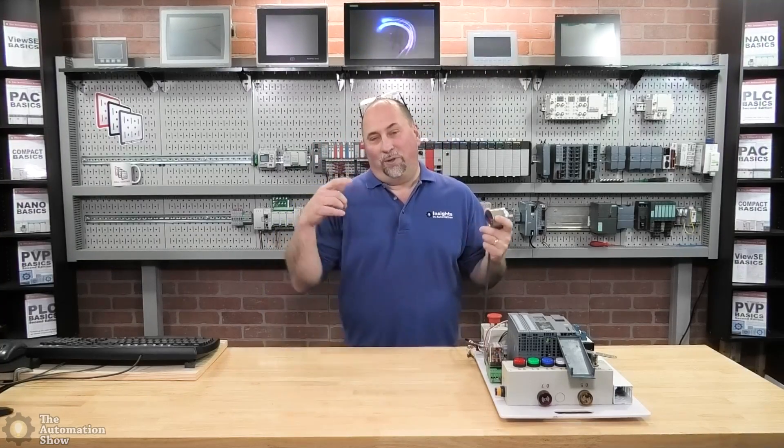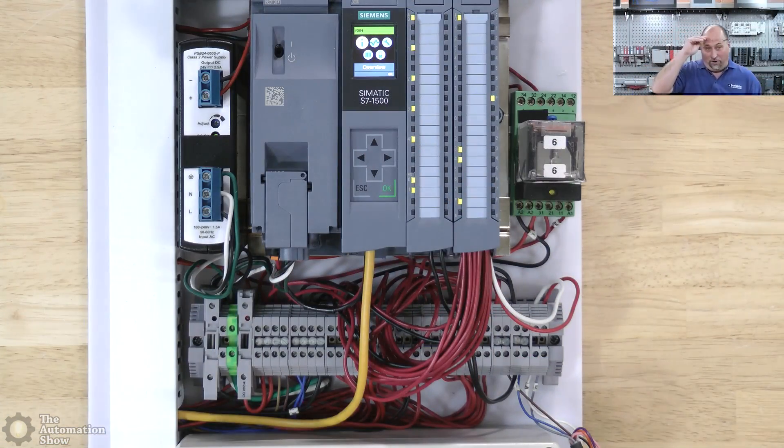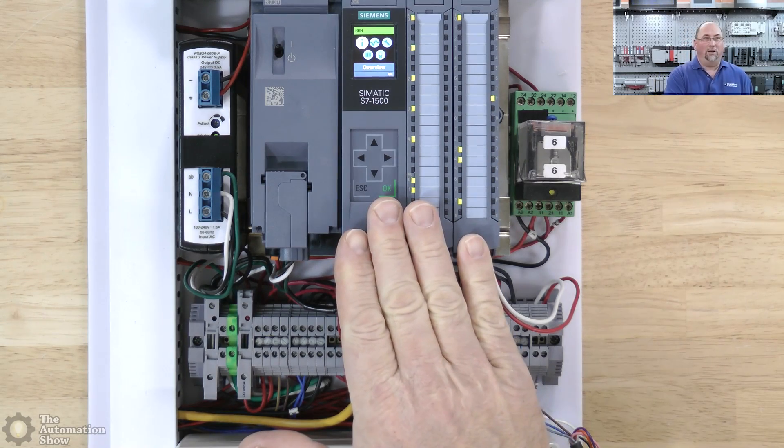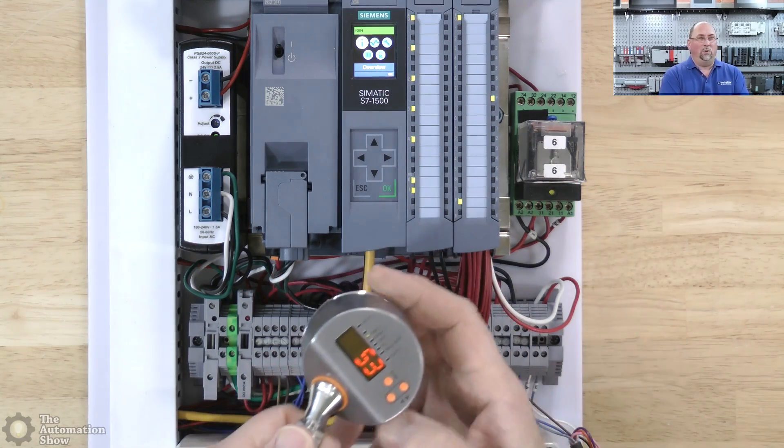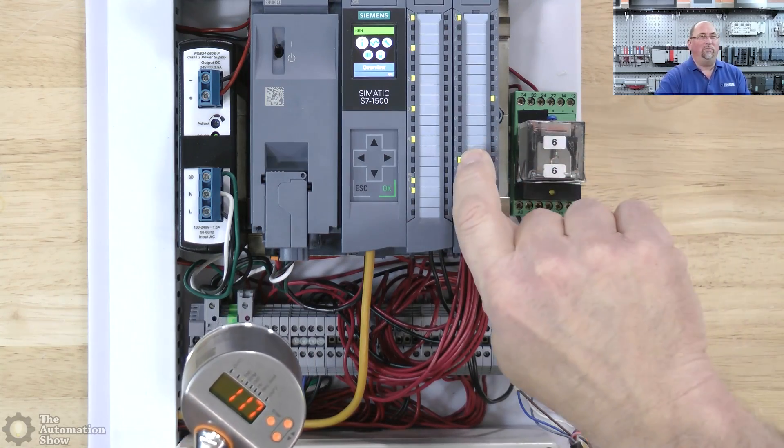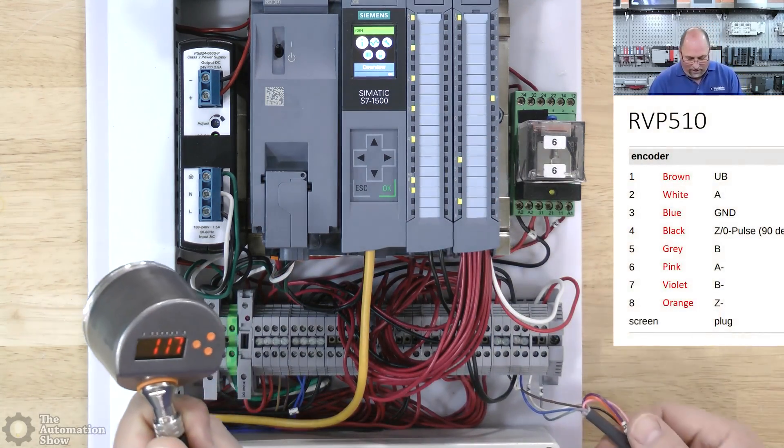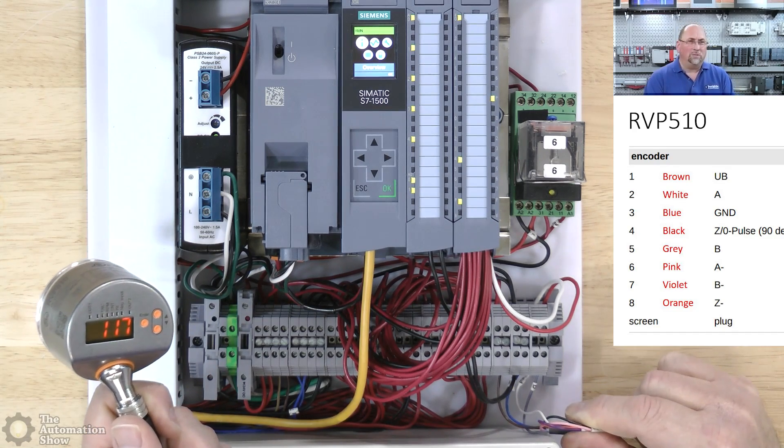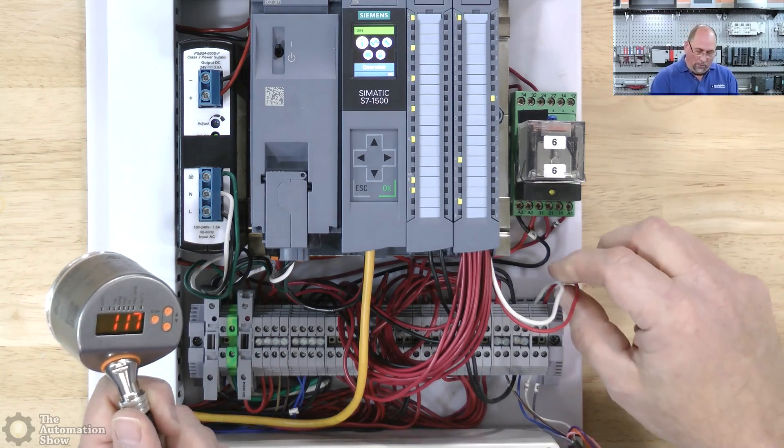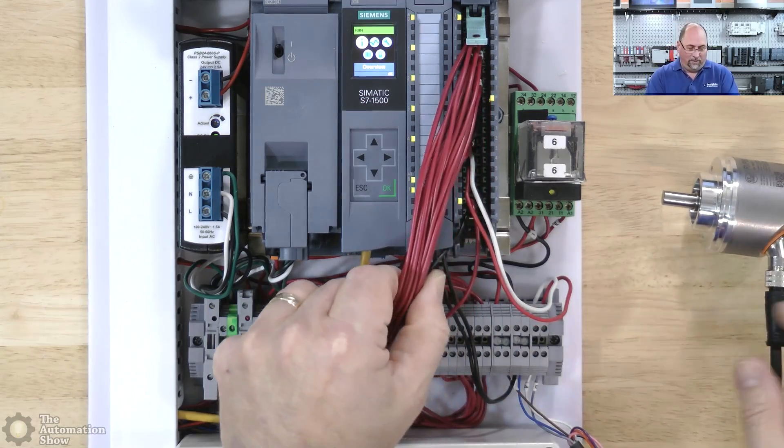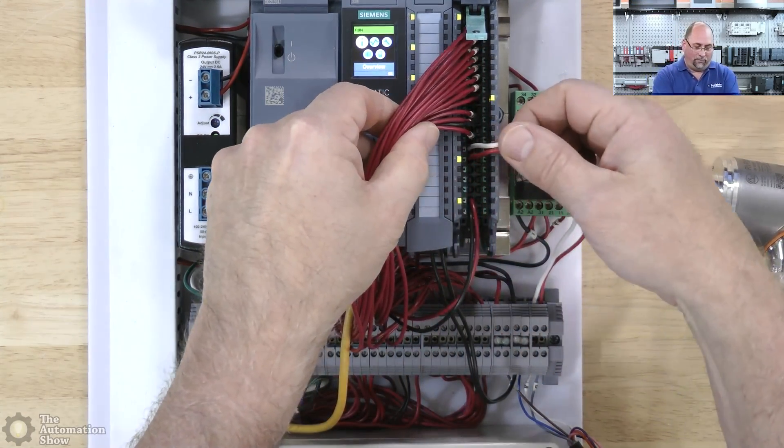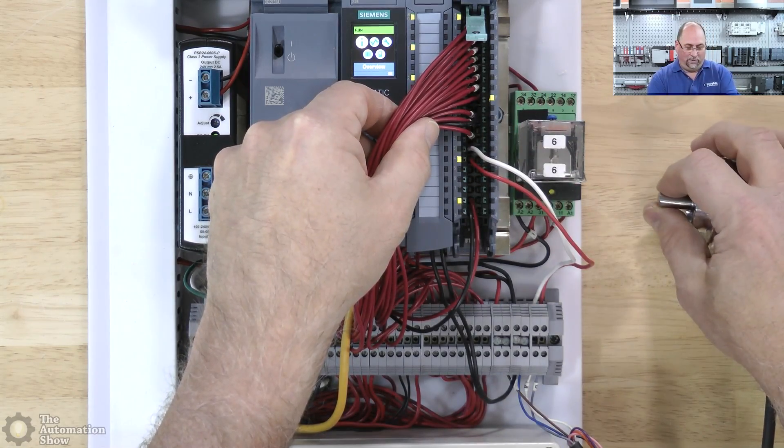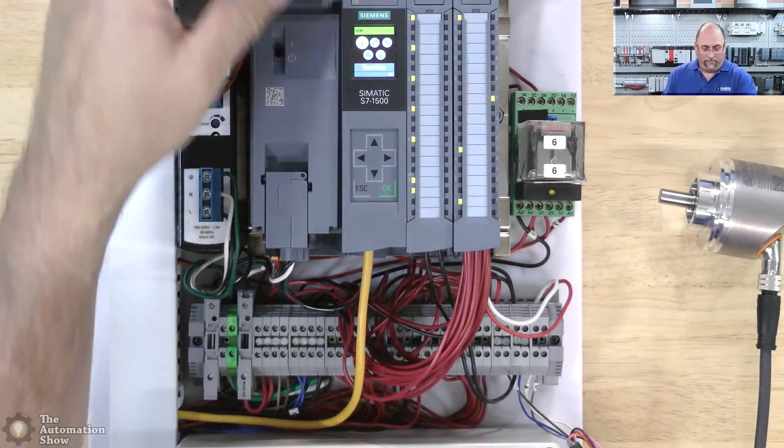So with that said, let's go ahead and first take a look at the encoder and the PLC itself. You can see here's the S7-1500 and I want to show you the encoder. As I turn it, you'll see two lights blink on and off, see that's three and four right there. And you can see we're wired in here. We got the encoder wired into plus and minus 24 volts DC and then we have the A and B going to the white and red, going into three and four. You can see that right there where they turn on and off. So that is the hardware side of everything.